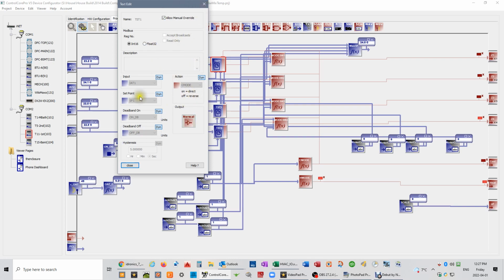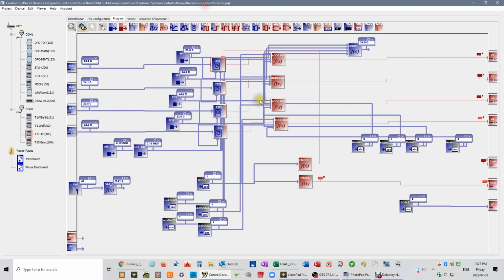So basically it's saying if the indoor air temperature reaches the set point minus the on dB, it's going to turn on the equivalent zone valve. And what it doesn't directly turn on, it is just providing a variable. Let me click on that to create these variables. So basically this is saying, is this true or false? And if it's true, it'll show that it's lit up. That then provides a true or false to the next call for the result from this block.